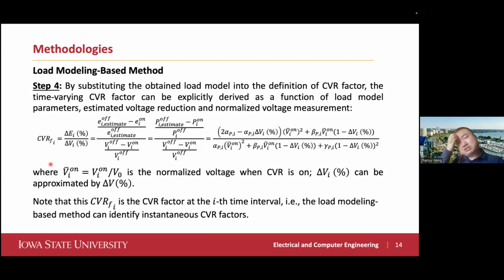But this CVR factor is only time varying — for each time window you get a CVR factor, that's why it has the index i. That's not exactly what utilities want, but it's true, because your load composition changes with time, so your CVR factor should also change with time.